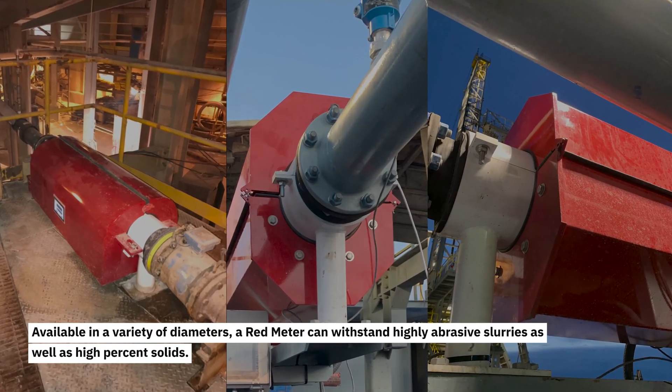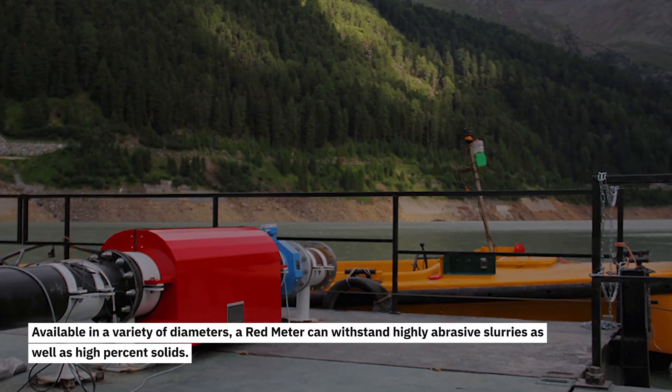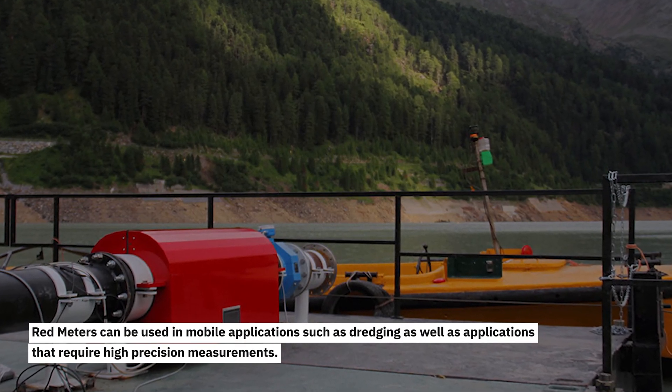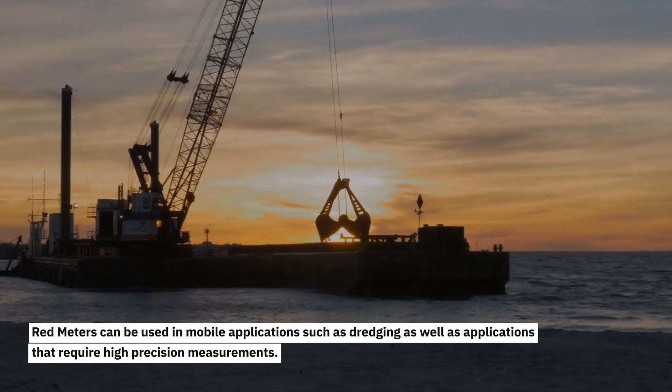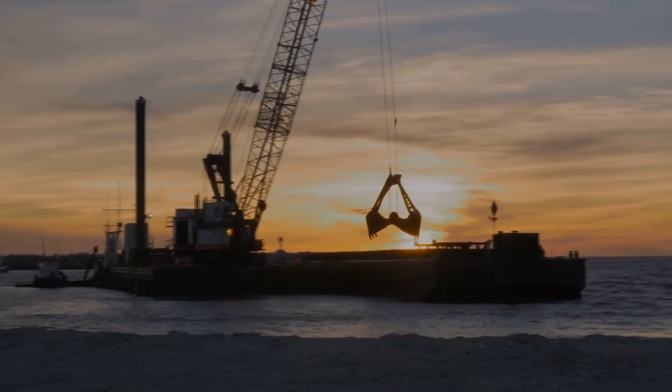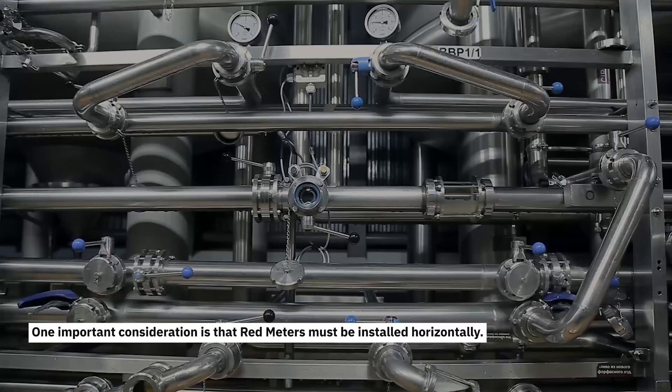Available in a variety of diameters, a Red Meter can withstand highly abrasive slurries as well as high percent solids. Red Meters can be used in mobile applications, such as dredging, as well as applications that require high precision measurements. One important consideration is that red meters must be installed horizontally.